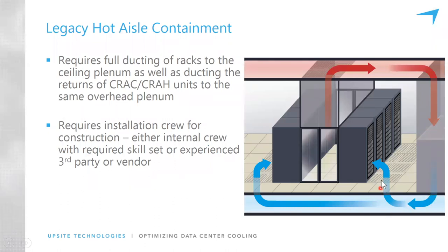I'll step back and answer one of the questions that's already been asked: what's better, hot aisle containment or cold aisle containment? Studies — both theoretical CFD analysis and in-the-field studies — have proven that hot and cold aisle containment, if done well, are equally efficient. And I emphasize that 'if' because it's a potentially big if.